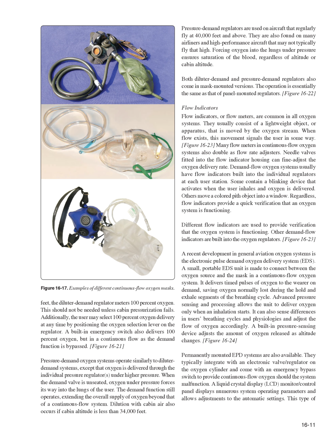A small, portable EDS unit is made to connect between the oxygen source and the mask in a continuous flow oxygen system. It delivers timed pulses of oxygen to the wearer on demand, saving oxygen normally lost during the hold and exhale segments of the breathing cycle.